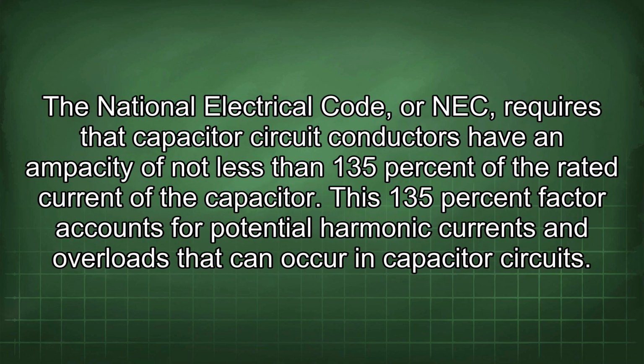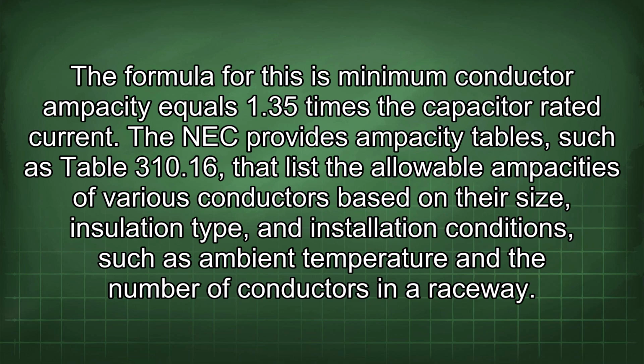The National Electrical Code, or NEC, requires that capacitor circuit conductors have an ampacity of not less than 135% of the rated current of the capacitor. This 135% factor accounts for potential harmonic currents and overloads that can occur in capacitor circuits. The formula for this is minimum conductor ampacity equals 1.35 times the capacitor rated current.